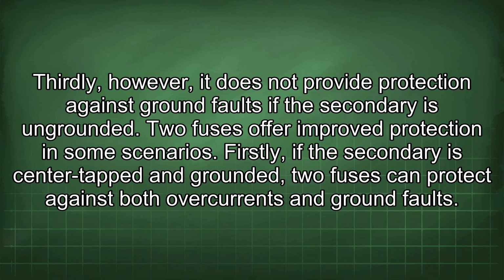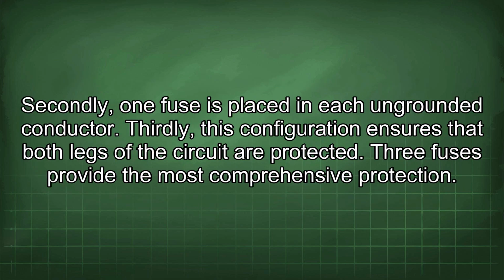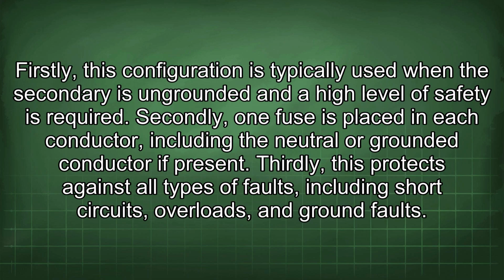2 fuses offer improved protection in some scenarios. Firstly, if the secondary is center-tapped and grounded, 2 fuses can protect against both overcurrents and ground faults. Secondly, 1 fuse is placed in each ungrounded conductor. Thirdly, this configuration ensures that both legs of the circuit are protected. 3 fuses provide the most comprehensive protection. Firstly, this configuration is typically used when the secondary is ungrounded and a high level of safety is required. Secondly, 1 fuse is placed in each conductor, including the neutral or grounded conductor if present. Thirdly, this protects against all types of faults, including short circuits, overloads, and ground faults.